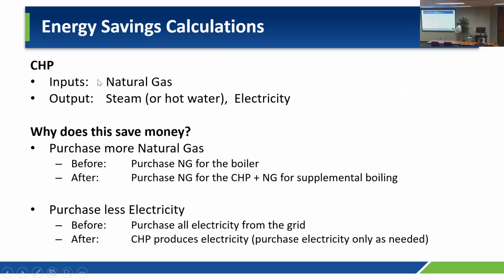What are my inputs? I'm going to have natural gas. What am I going to get out? Either steam or hot water, and electricity. Why am I saving money? Well, in this case my natural gas bill is probably going to go up if I use a natural gas fired system. Before, I was purchasing natural gas just for my boiler or hot water heater; now I'm purchasing natural gas for my combined heat and power system, plus whatever I need for any leftover supplemental boiling. This means my natural gas bill goes up, but my electricity bill goes down, because before I was purchasing all my electricity from the grid—now I can subtract off the electricity produced by the CHP, both in kilowatt demand and kilowatt-hour consumption. So you can calculate savings.